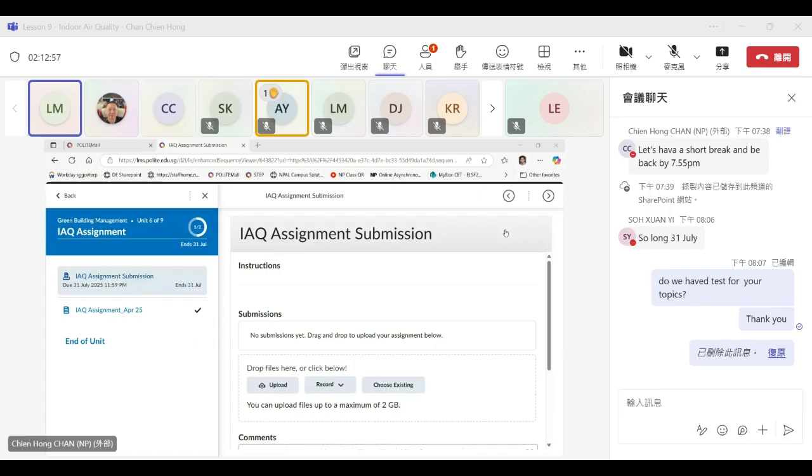So the flow was as per normal, and our AHU fan speed is also as per normal, 25 Hz. So nothing was excessive, but we just could not find out what was the real cause of this mold that keeps appearing on this floor only. And you are saying that the mold appears on the false ceiling panel? Yeah, ceiling board.